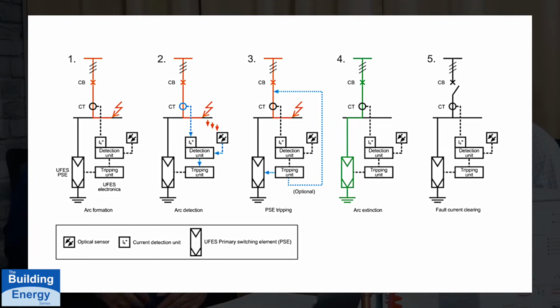Yeah. But at the same time, you want to have optimal operator safety, right? Yeah, of course. And basically, with this system, as I mentioned, it will collapse the arc voltage in less than 4 milliseconds. So all of that current is being now directed to ground, and then the upstream breaker will then actually trip, isolating that fault in 3 to 5 cycles.